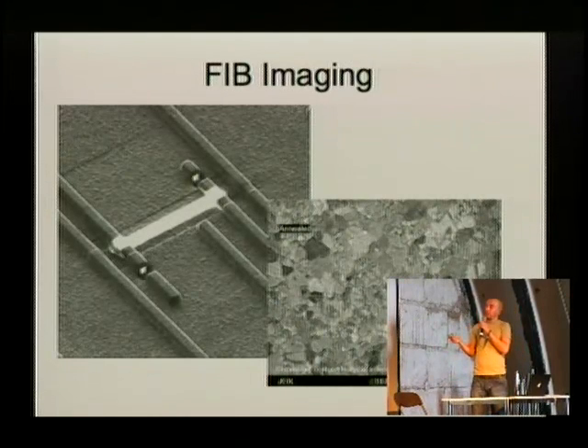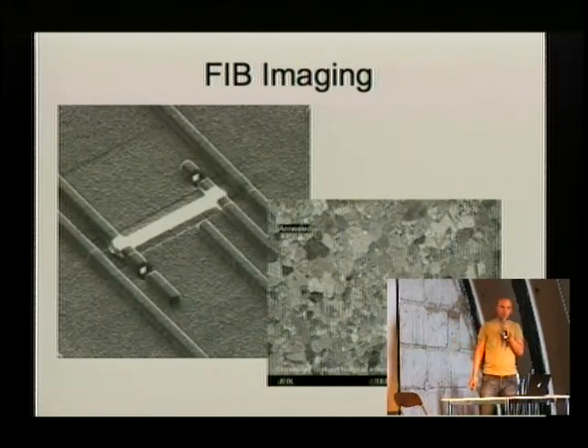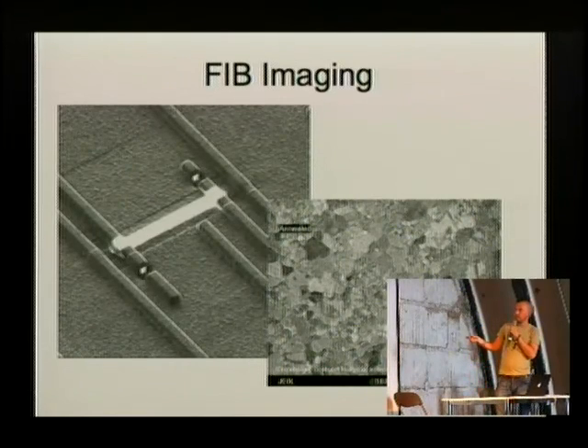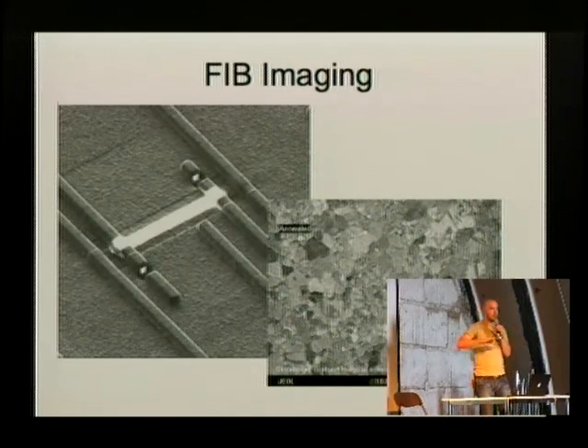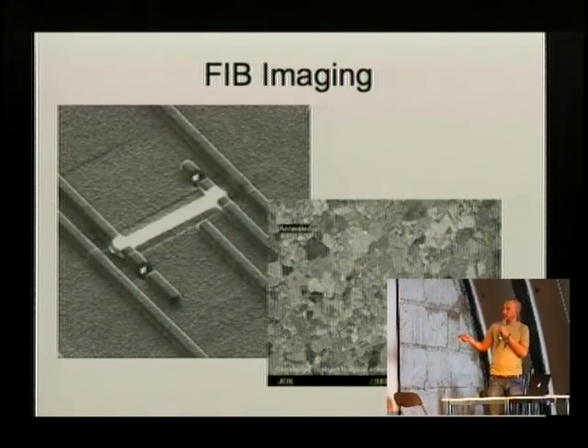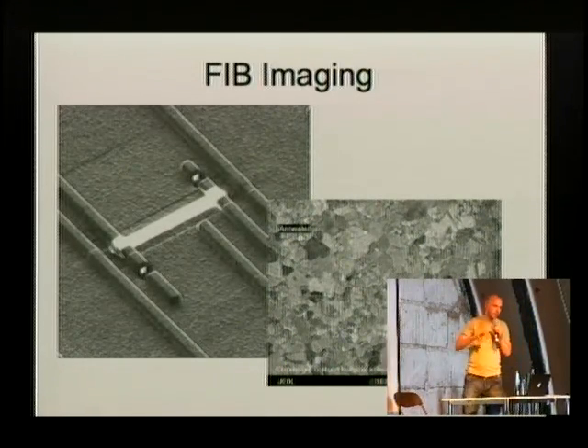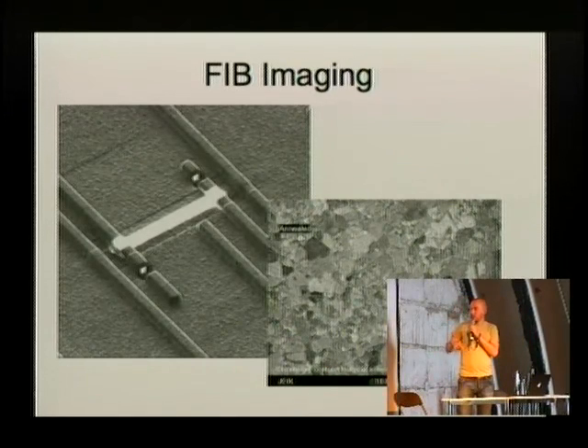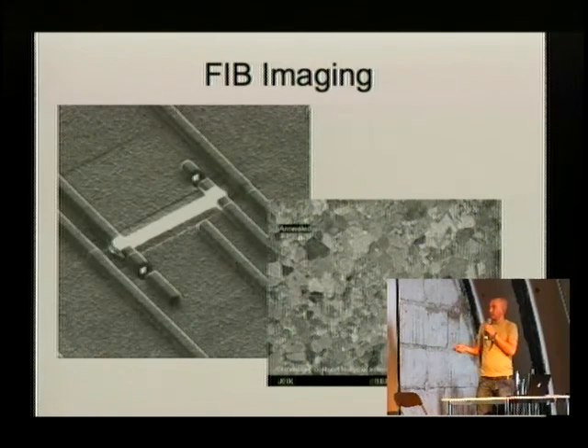So you can use the FIB, the focused ion beam, for imaging. This is pretty straightforward. If you have a very low dose, you get a nice signal. It basically looks like an electron microscope picture. Here we have some metal lines, and nothing much different than an electron picture. There's only one effect. If you look at metals that have a granular structure, even though the metal itself is flat, you see all these small islands. This is because the metal lattice is oriented differently in the grains of the metal, and you get channeling effects. That reduces your secondary electrons, so although the surface is flat, it looks structured in the picture.